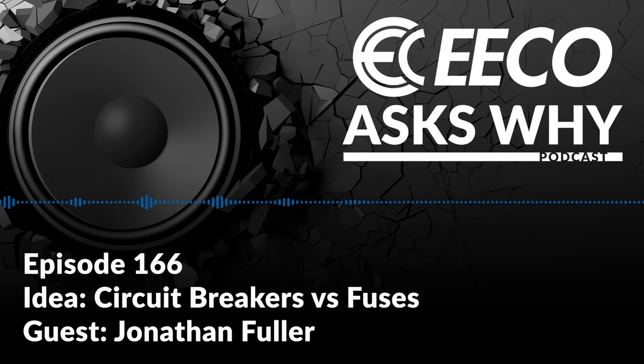Right. Absolutely. I'm thinking back to a previous episode we did, so far as when a breaker trips, it typically trips for a reason. That doesn't mean let's just go crank it up a little bit more. Or if it's a 30 amp fuse that blew, maybe we just need to go to 35. Typically these devices are engineered with the right proper schemes to protect that equipment. So let's talk about trip curves on breakers, because that's going to help determine the right type of breaker that we want. So how do we select that proper trip curve?